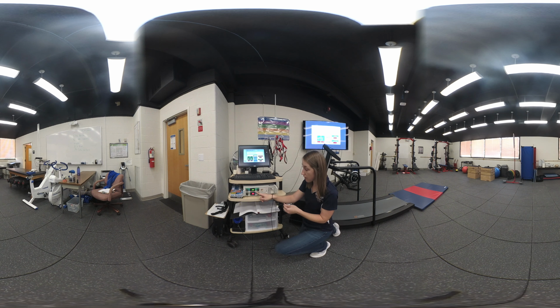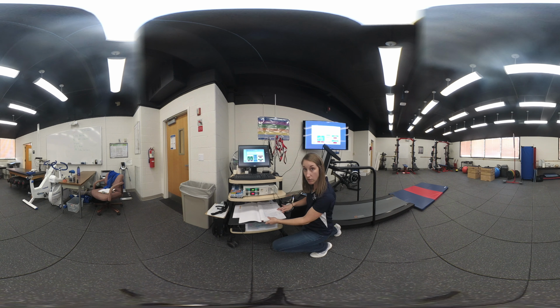If you look at the front of the metabolic screen, on the top it has what it's sampling for oxygen, and at the bottom it has what it's sampling for carbon dioxide. We would expect in the room for it to be sampling somewhere between 20.8 and 21.1 for oxygen. And we would be expecting it to sample somewhere between 0.04 and about 0.07 for carbon dioxide. In case you forget those numbers, they're in the instruction manual on page 8 on the metabolic cart. It tells you exactly what numbers you need whenever you're calibrating.